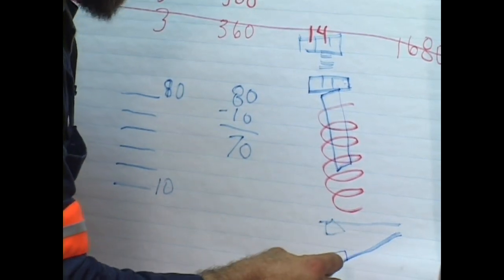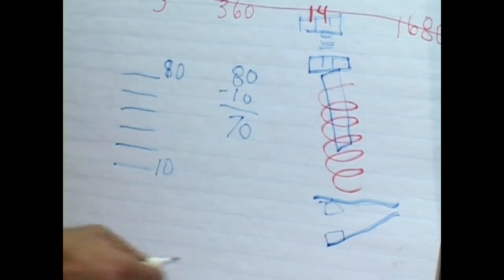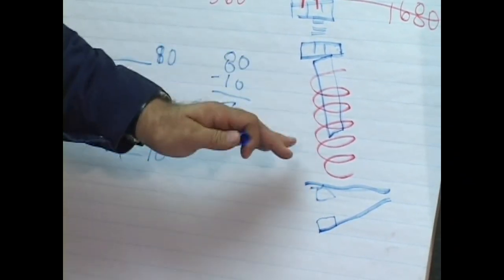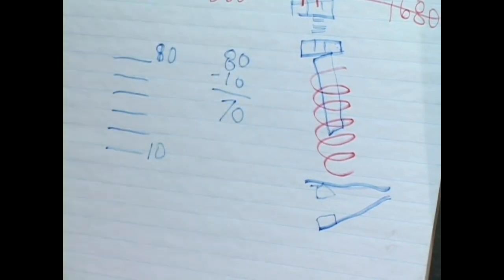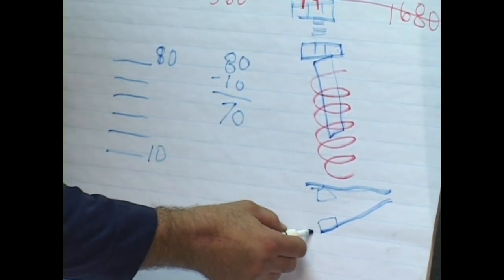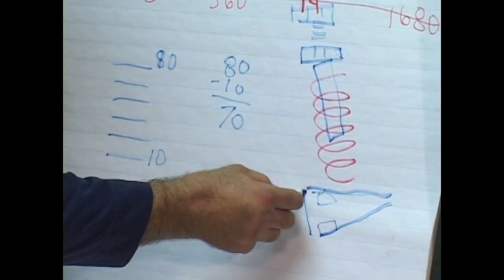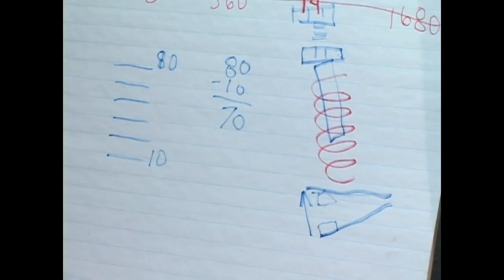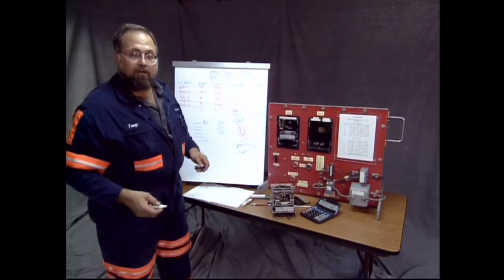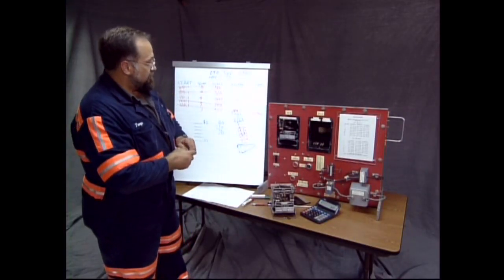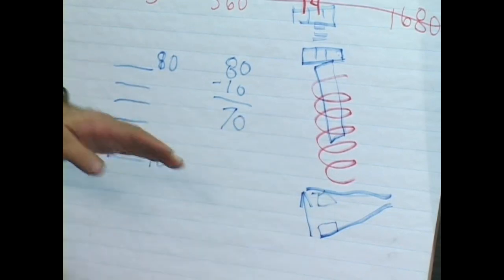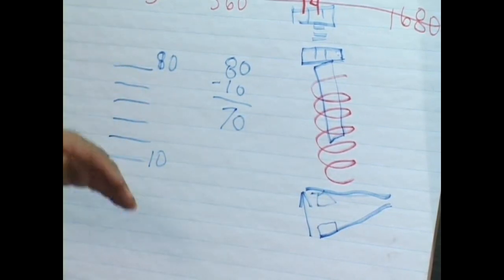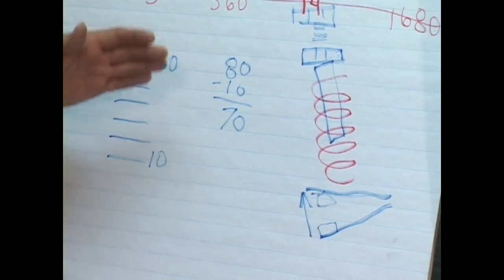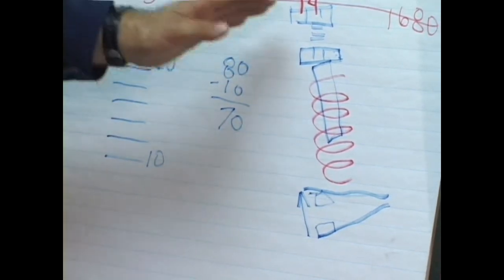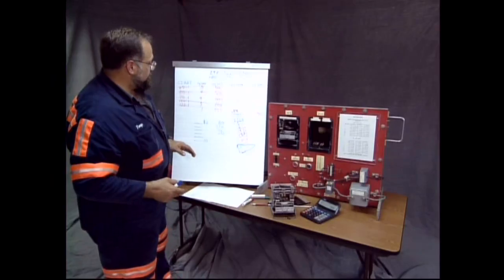A contact point that when this coil becomes a magnet, the core is magnetized, it will actually lift these contacts and make a contact to operate the relay. So, the farther down it's adjusted, the less current has to flow to bring about the same action here, to lift and pick up this relay. That's what we're going to adjust, is that core.